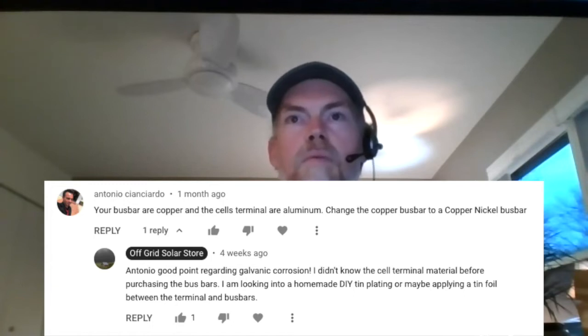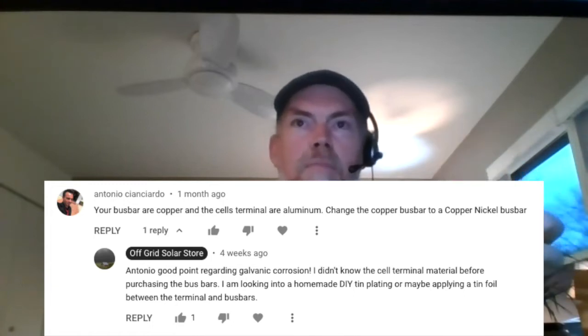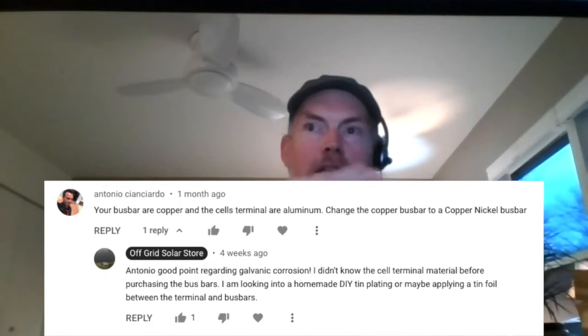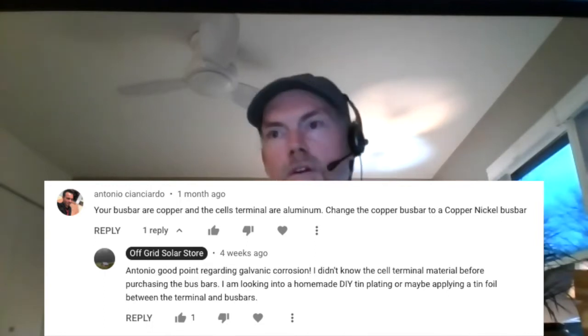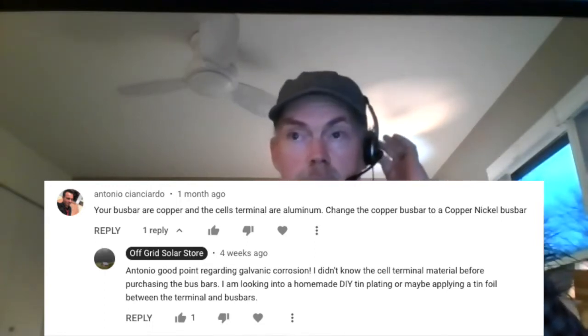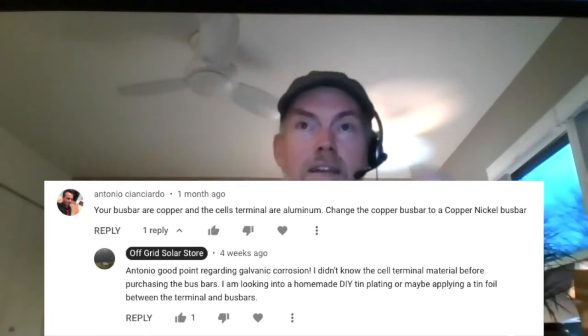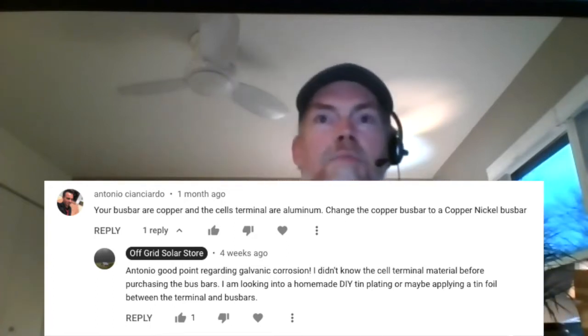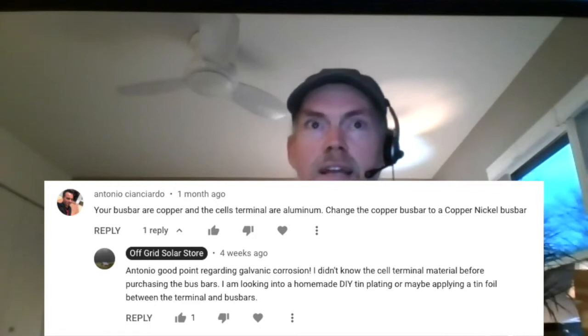So when you have aluminum battery terminals touching copper bus bars, over time, especially if you have a really humid climate, that can cause problems. Good thing that where you're at is very dry.